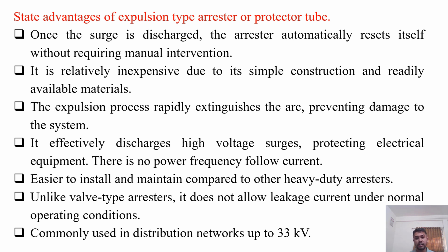So there are several advantages. Some are listed over here. Once the surge is discharged, the arrestor automatically resets itself without requiring manual intervention. It is relatively inexpensive due to its simple construction and readily available materials, so it is cost effective. The expulsion process rapidly extinguishes the arc, preventing damage to the system, equipment or operating personnel. It effectively discharges high voltage surges, protecting electrical equipment. There is no power frequency follow current, means back current.